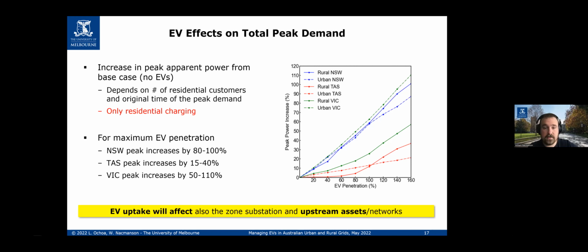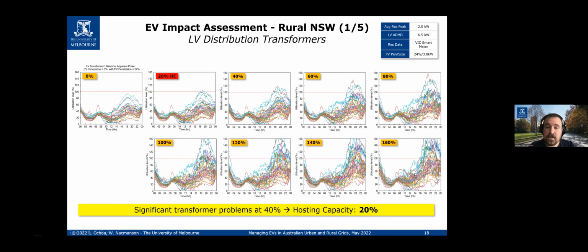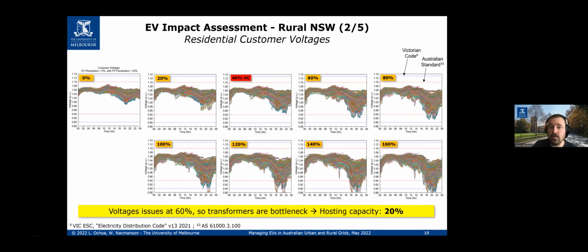So if we move to the next slide, please. When we're talking about hosting capacity, as we mentioned earlier, it's all about, are the assets within limits? Are the voltages okay? So here's an example of rural New South Wales with the LV distribution transformers. And we see that once we hit 20% and beyond, we start getting issues. So we can say, okay, 20% when we talk about the LV distribution transformers is the hosting capacity for this feeder. At 40, 60, 80, we start getting some transformers overloaded, not all of them, and that ultimately limits the hosting capacity for the whole HV feeder. Yes, there's capacity on other transformers, but if we take the whole HV feeder as a whole, that is the bottleneck.